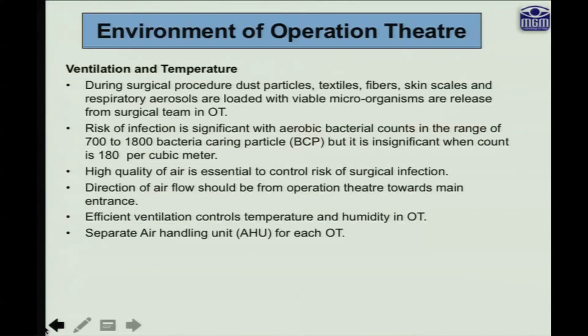Ventilation and temperature maintain the environment of the operation theatre. It is very important. During surgical procedures, dust particles, textile fiber, skin scales and respiratory aerosols loaded with viable microorganisms are released from the surgical team in the OT. Risk of infection is significant with aerobic bacterial counts in the range of 700 to 1800 bacteria-carrying particles, but it is insignificant when the count is 180 per cubic meter.